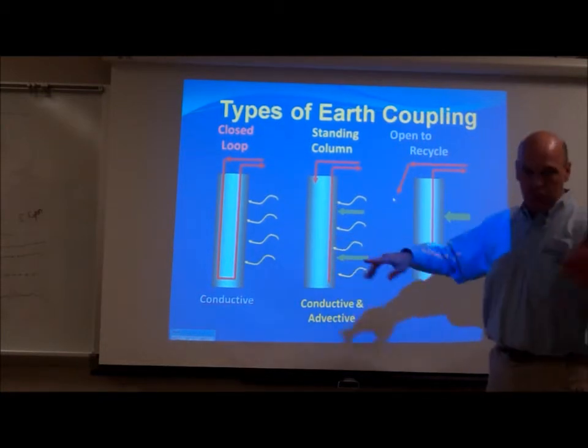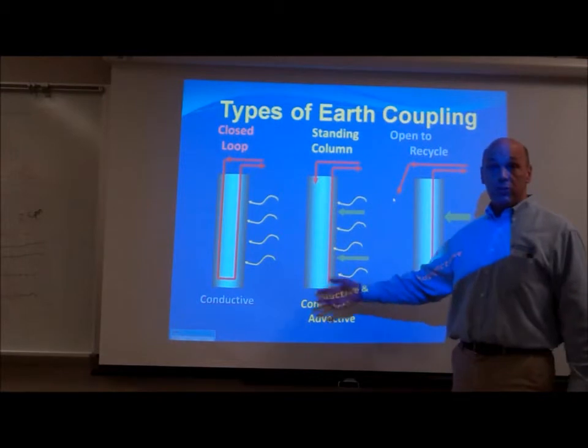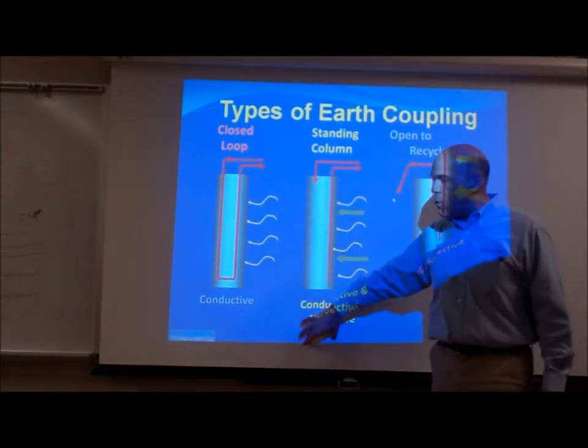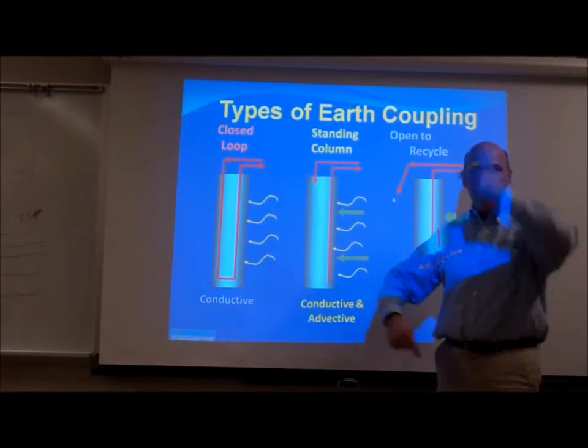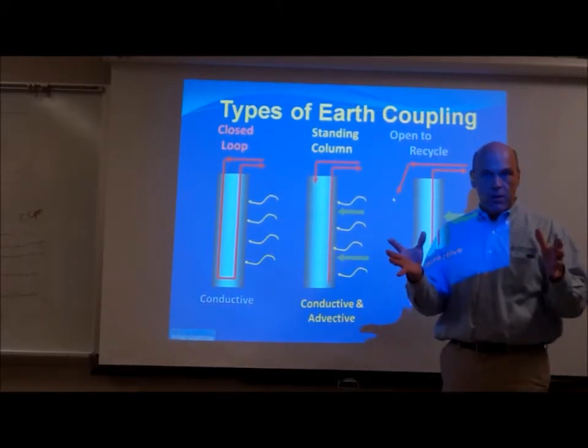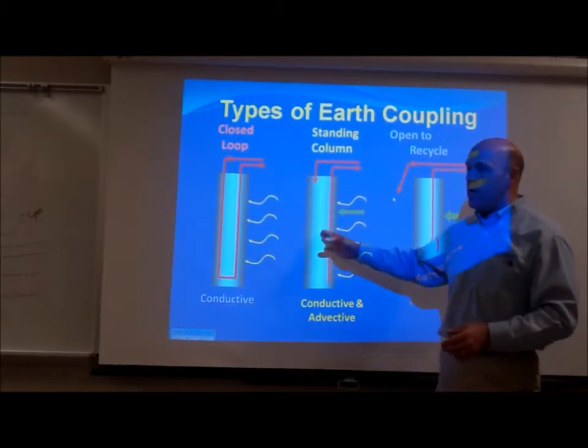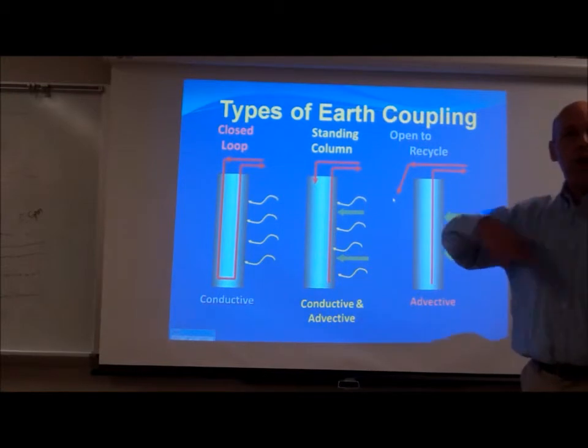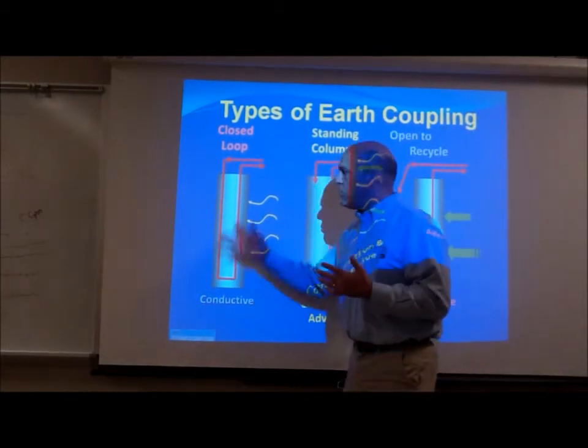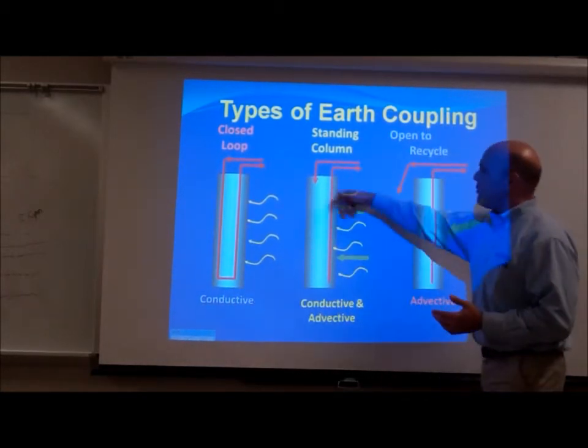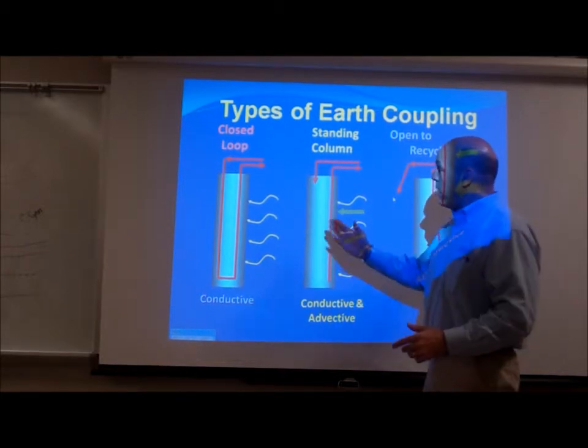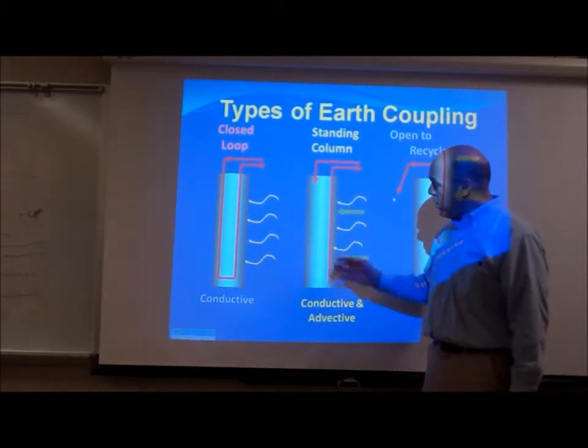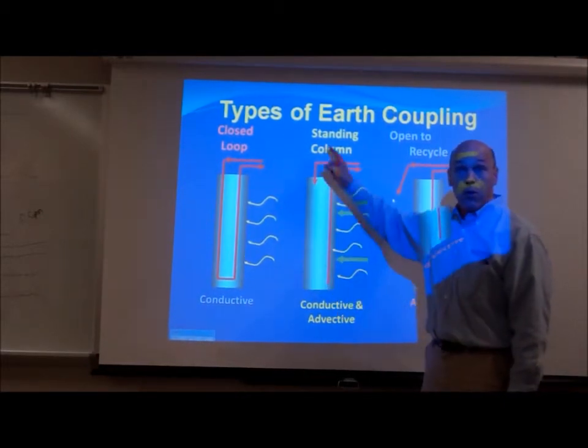There's really a hybrid of the two. Here I've got a bedrock well, very common in New England. I take the water out of the bottom, go across my heat exchanger, and return 100% of it back to the top. So the length of that wet borehole becomes my heat exchanger — my conductive space by which I'm making a connection to the earth. Like the open system method, there is no intermediary between the earth and the fluid going across the heat exchanger. Let's say I come in at 50 degrees and go back at 45 — that's my delta. By the time it travels back down again, hopefully the bore is long enough with enough mass touching the earth that by the time I get to the bottom and I'm on my way in again, it's back to 50 degrees. It does that over and over again.